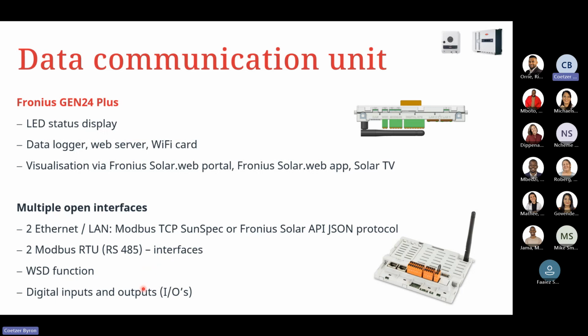Lastly is our digital inputs and outputs, or IOs. If we want to do intelligent load management, we can use the inputs and outputs to control the unit separately, or to trigger different relays to open and close with simple PV surplus that's available.